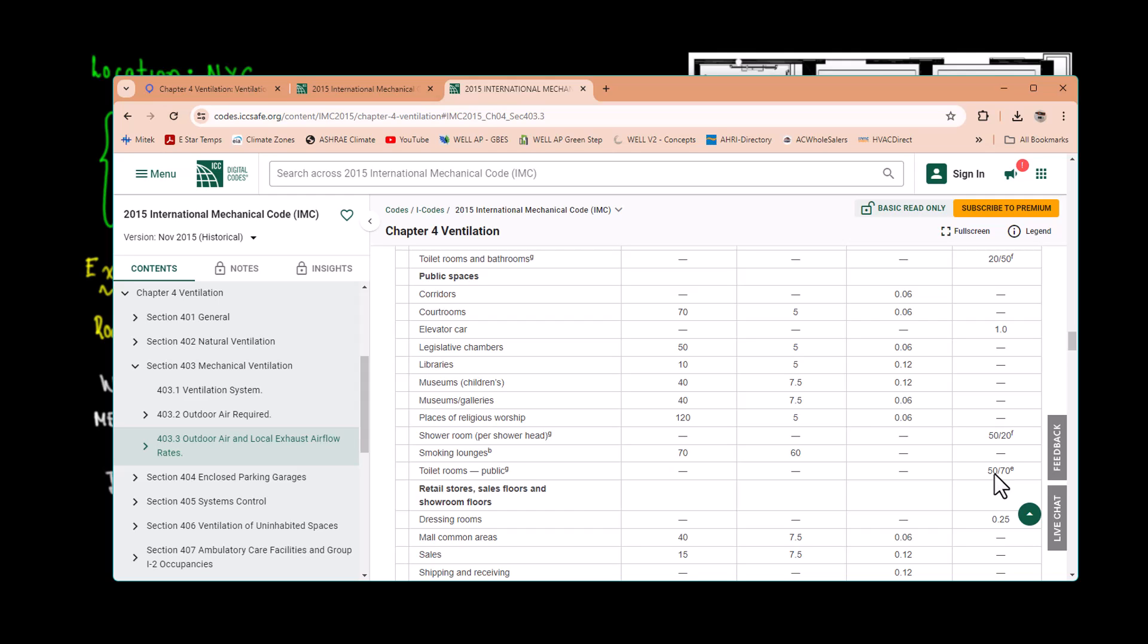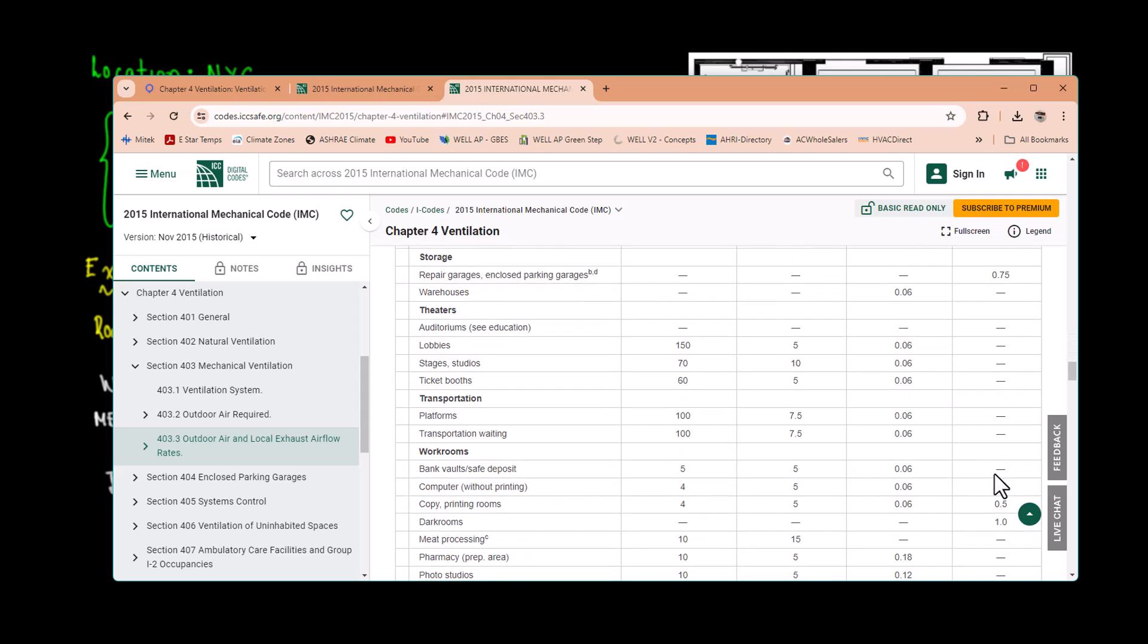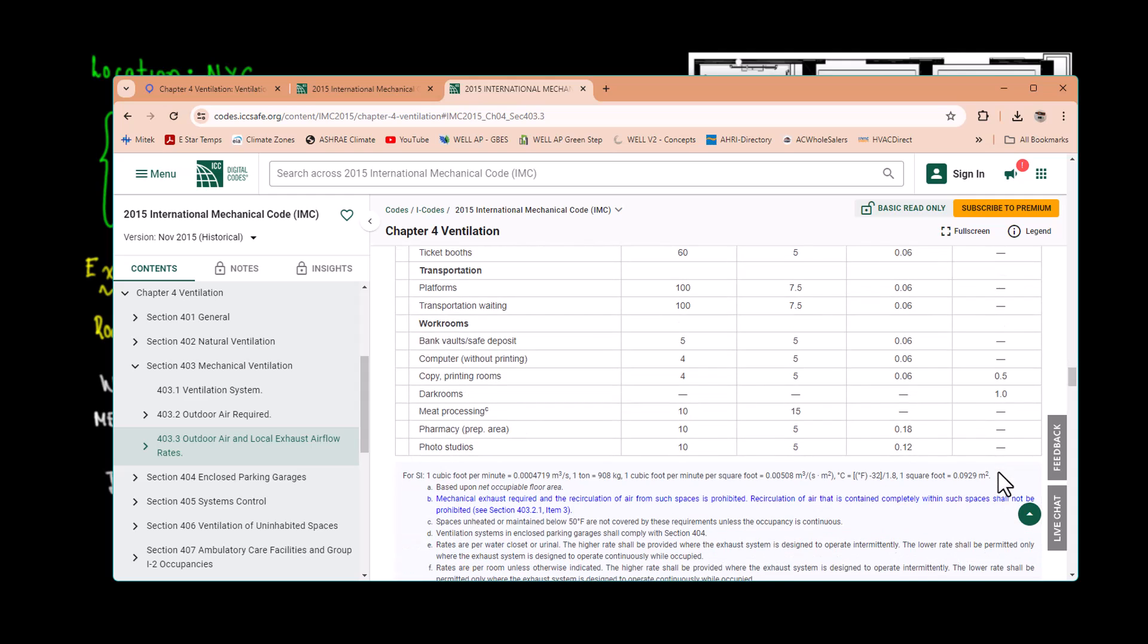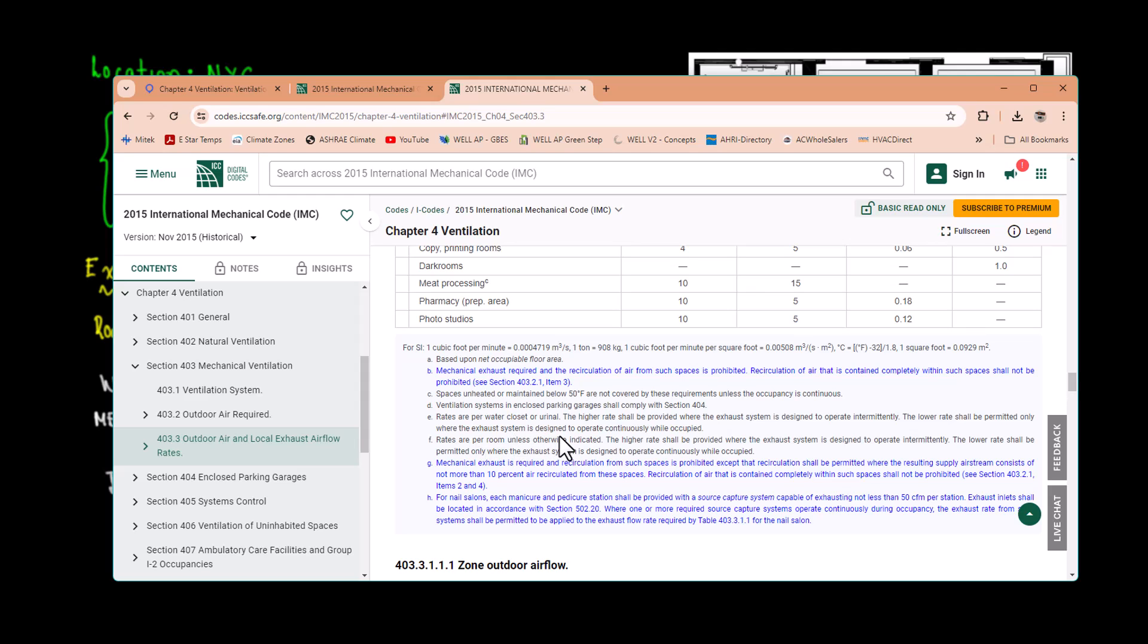We go down and you have the public spaces, toilet rooms. It says 50 and 70 with an 'E'. The E means per water closet or urinal as we were explaining in the previous video. It's pretty much the same: CFM per square feet and 70 for intermittent and 50 for continuous. Rates per water closet or urinal. The lower rates are permitted only where the exhaust system is designed to operate continuously while occupied.